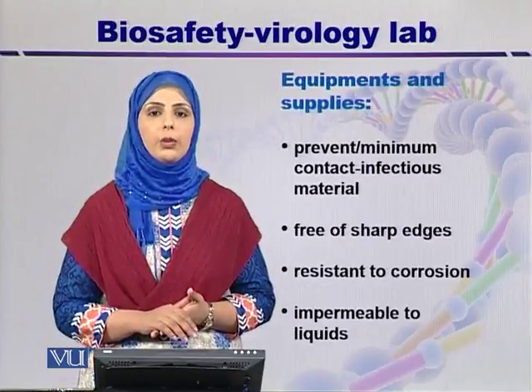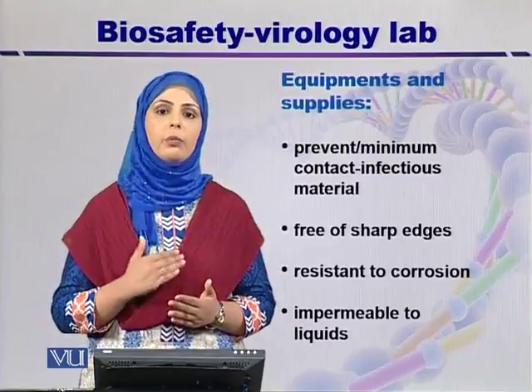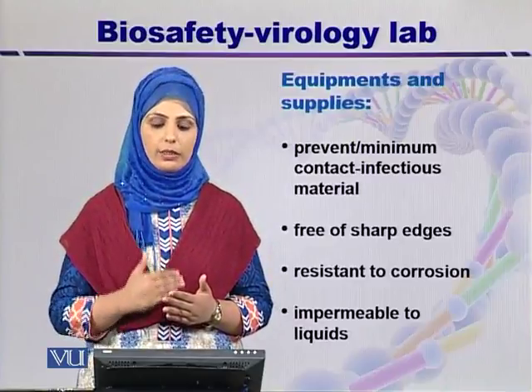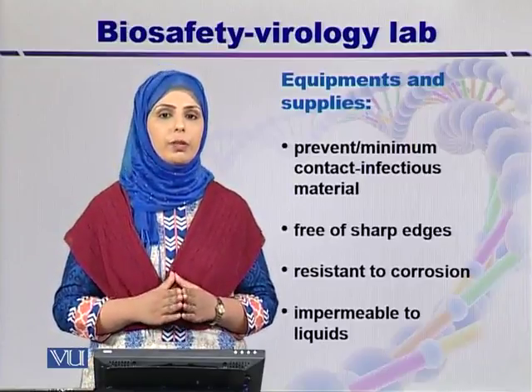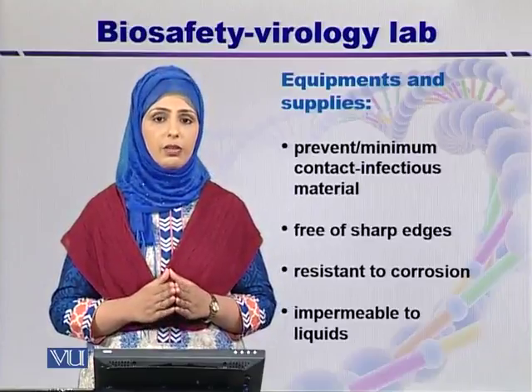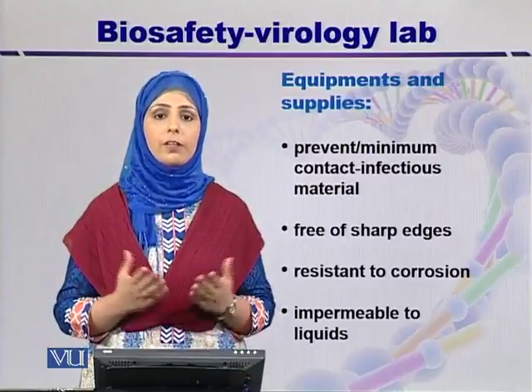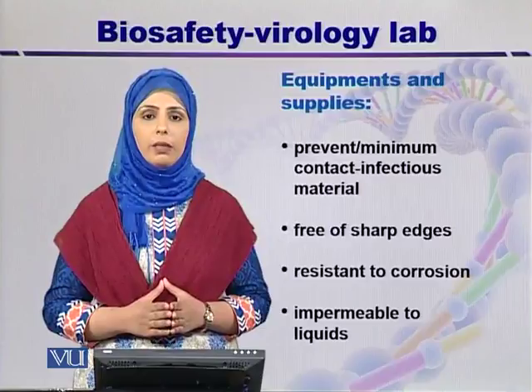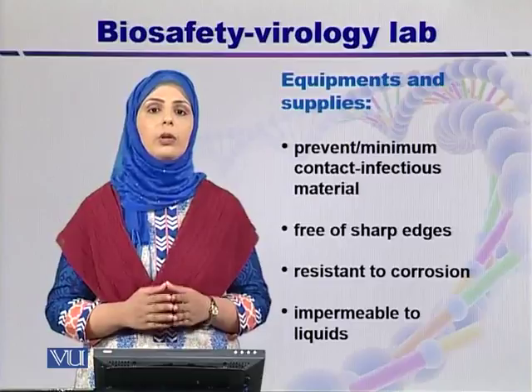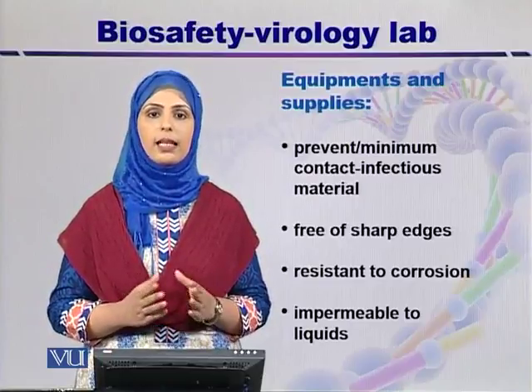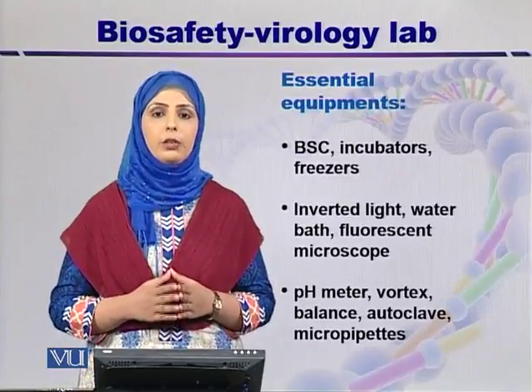The third element is equipment and supplies. Equipment must minimize contact between personnel and infectious material, be free of sharp edges, and be resistant to corrosion. If breakage occurs, decontaminate first. Equipment parts should be impermeable to liquids and chemicals. Equipment is divided into two groups: essential and desirable.